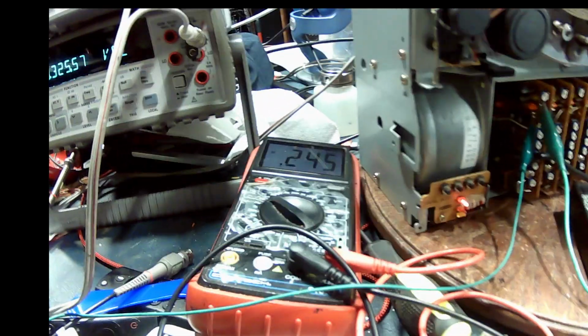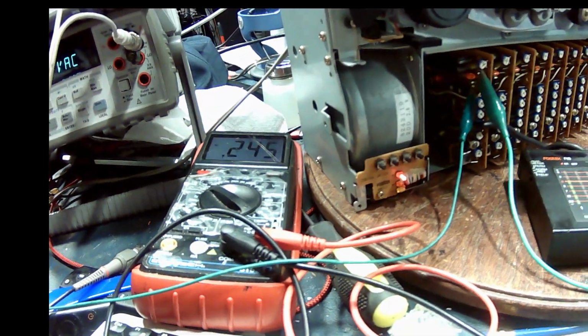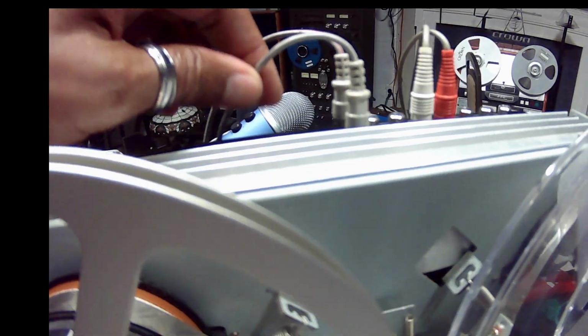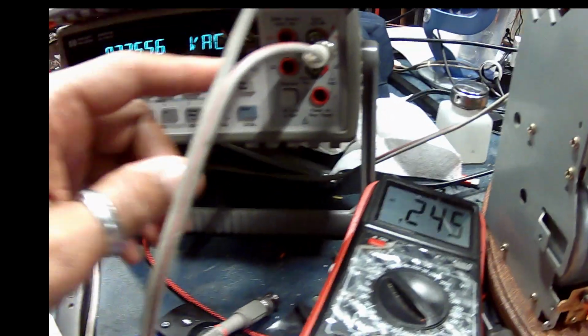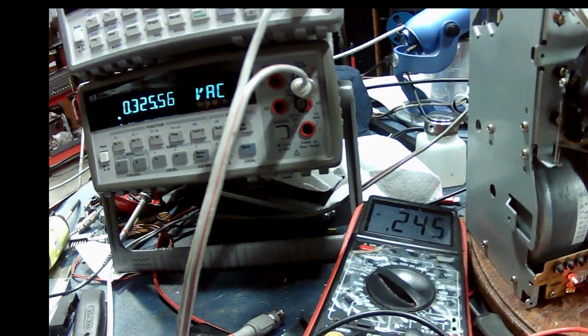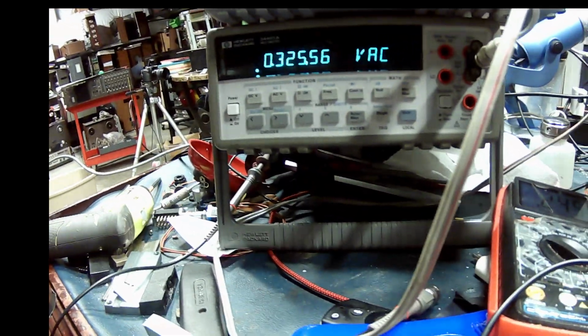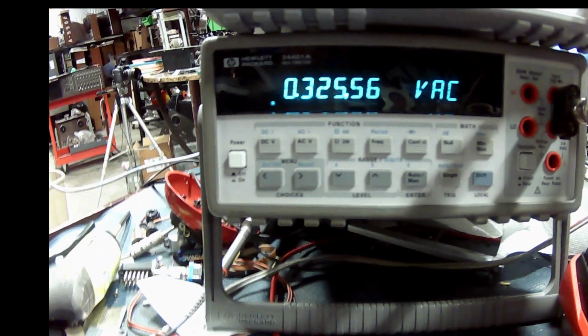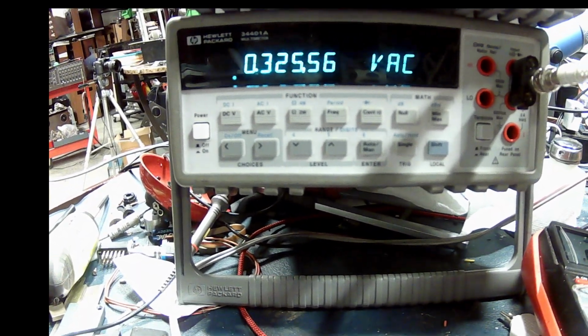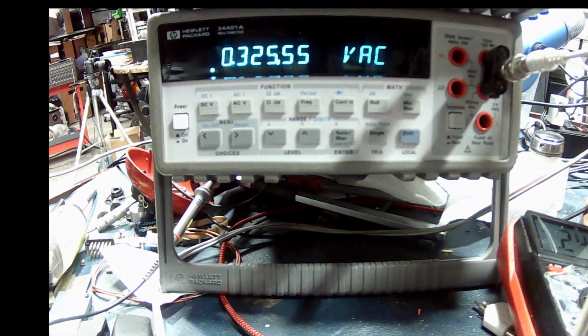Having said that, I normally skip this part because the next step is we're supposed to monitor the output of the unit. This is the input going in from the signal generator. This is the output, and it's going into this very accurate multimeter. It tells me that we should read 0.3 volts plus or minus 1 dB at the output, and we're reading 0.325. I'm not going to try to do the math in my head, but a little bit high. We want to get it right at 0.3 volts.